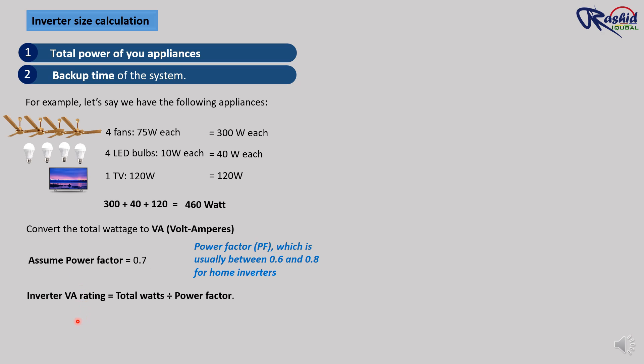The formula to convert watts to VA is: inverter VA rating equals total watts divided by power factor. So in our case, total watts is 460 watts as we calculated, divided by 0.7 power factor. So after dividing this value we get 657 VA.